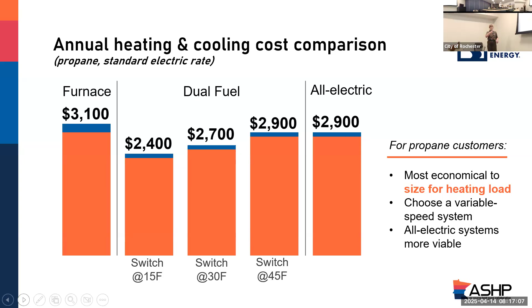A quick call out here: when it's more economical for the heat pump to take on more of that heating load, we recommend sizing closer to the heating load, but we want to make sure not to be oversized for cooling. That's really important and really difficult in Minnesota's cold climate, given how much larger our heating loads are than our cooling loads. If you're oversized for cooling, the equipment will short cycle and you won't get those benefits we talked about, like longer run times, better filtration, dehumidification, comfort, and indoor air quality. It's a tricky line to toe, you want to optimize operational costs as much as possible, but ensure the customer is still comfortable in the cooling season.